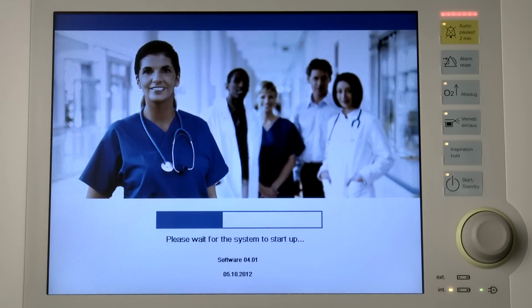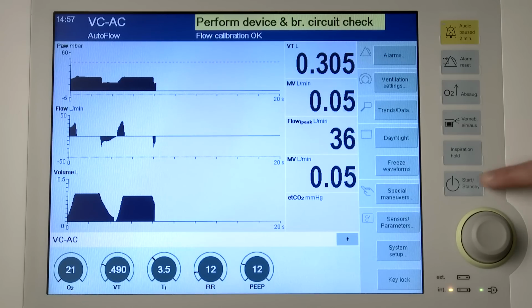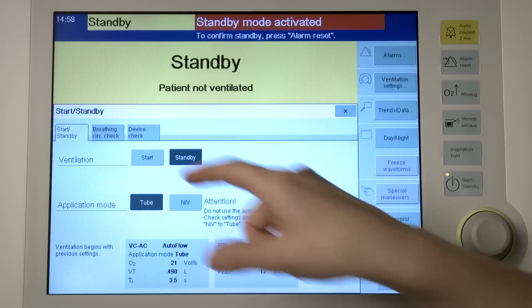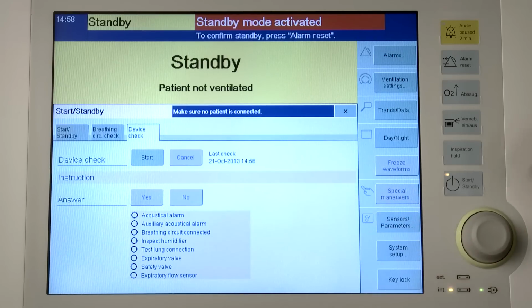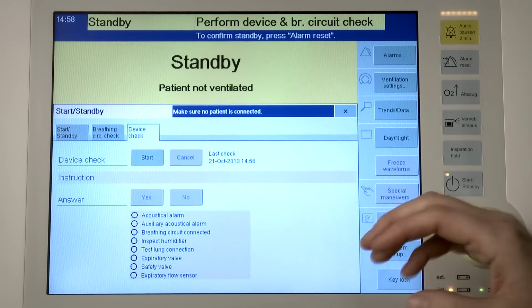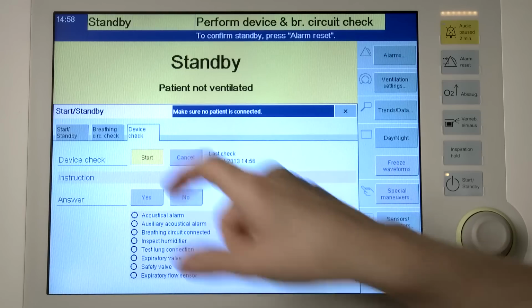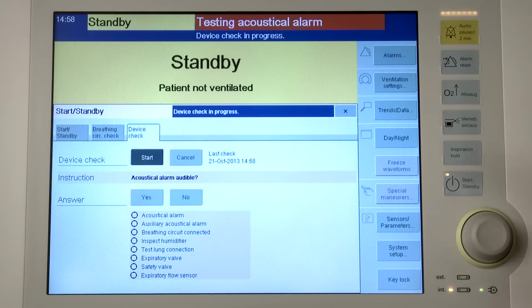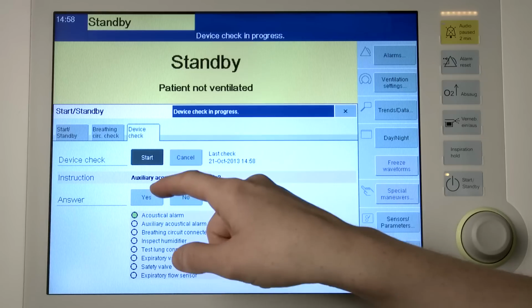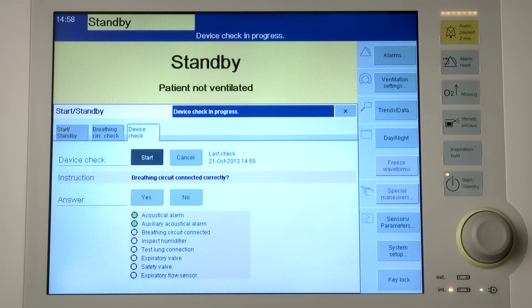Turn on Savina 300 and subsequently press the Start Standby key. Then touch the Device Check tab. There, Savina 300 displays the individual test steps in a list. Touch the Start button and confirm with the rotary knob. Answer the questions in the instruction field by touching the buttons Yes or No.